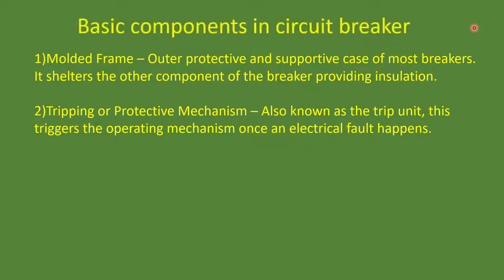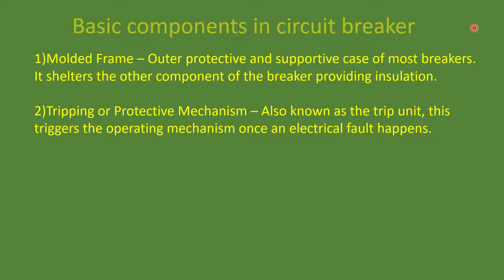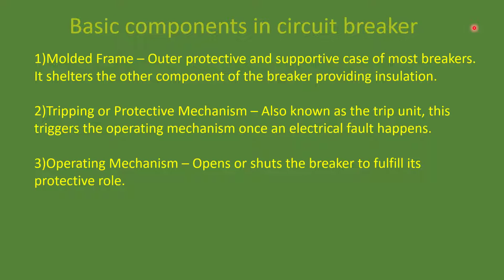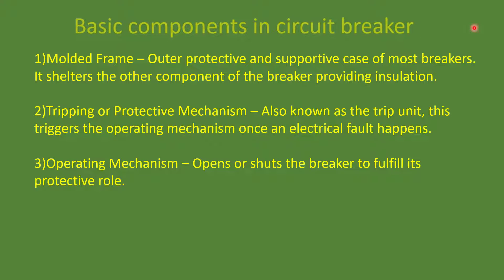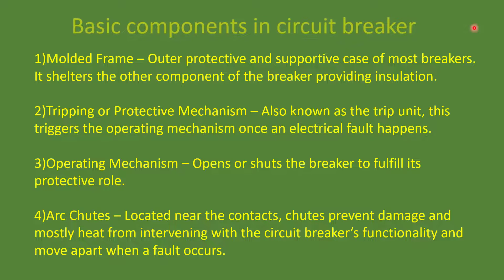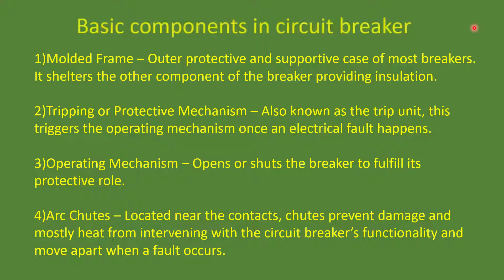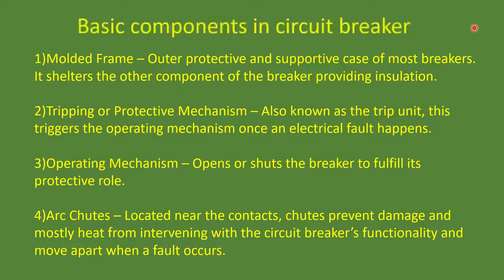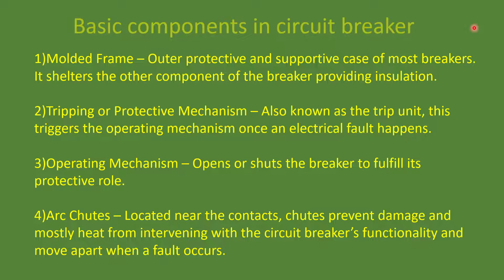The second component is the tripping or protective mechanism, also known as trip units. This is a sensing mechanism — it sends a signal to the operative mechanism for opening and closing of the circuit breaker. The third is the operative mechanism, used to open or close the circuit breaker. The fourth is the arc chute. When we suddenly disconnect the circuit breaker there will be an arc produced due to ionization of air. The arc chute is located inside the circuit breaker and is used to extinguish this arc.